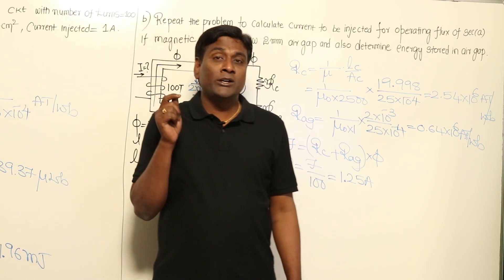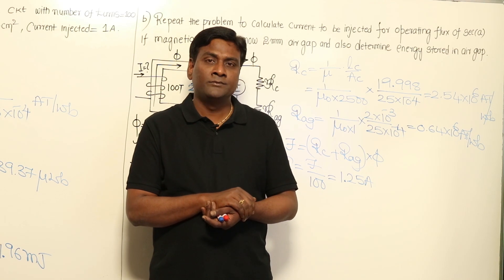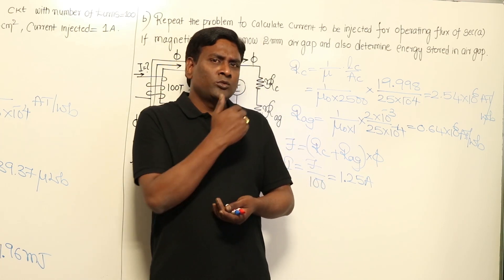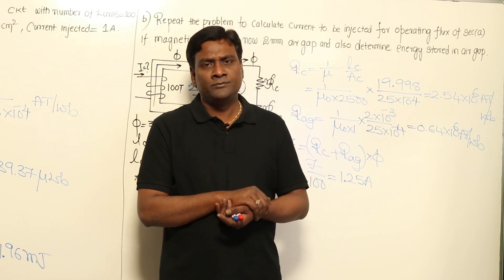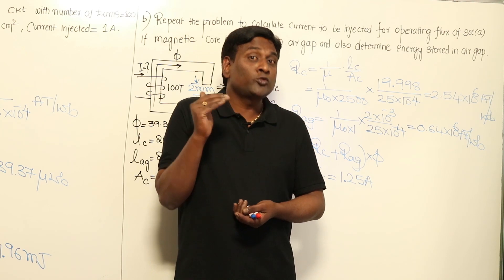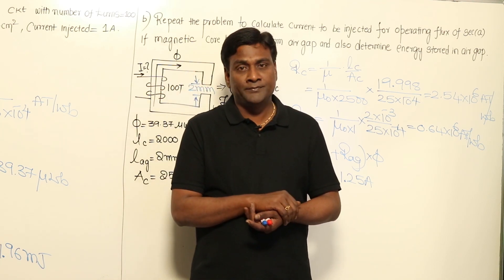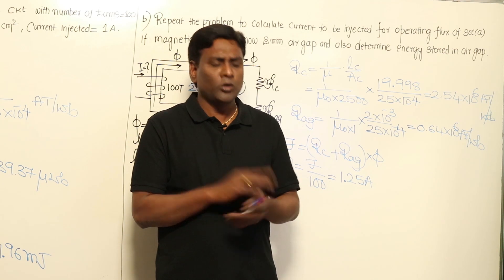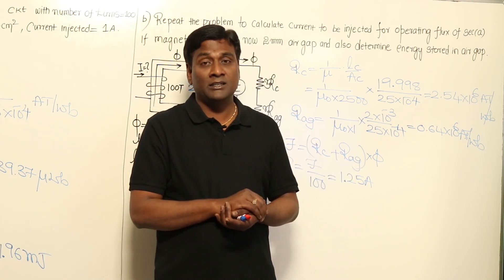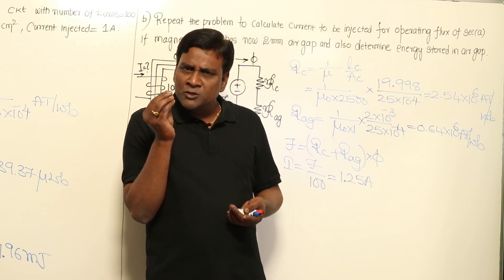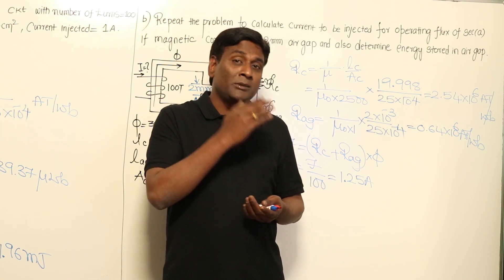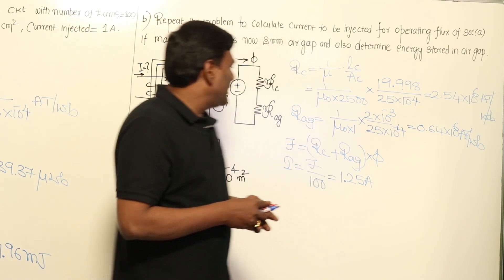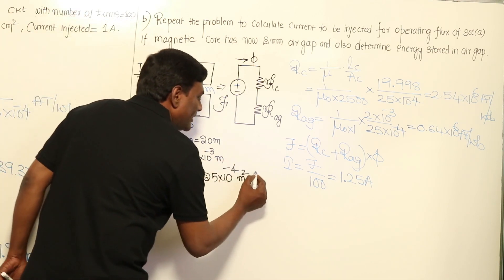Observe the difference: in the previous problem, 1 ampere was sufficient to produce 39.37 micro webers of flux. But in rotating machines, an air gap is compulsory, and to produce the same flux, the current must increase by 25%. That is why the no-load current of a transformer is only 2–6% of full load current, but in an induction motor it is 30–45%, because the induction motor has an air gap.